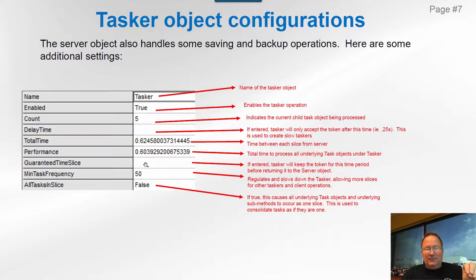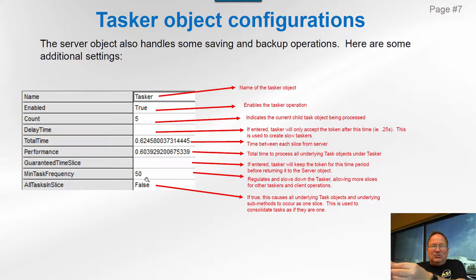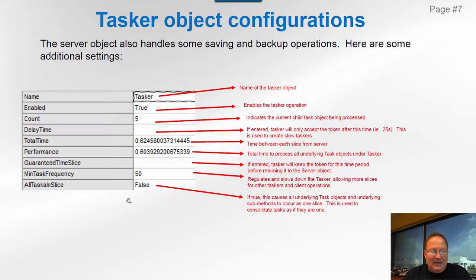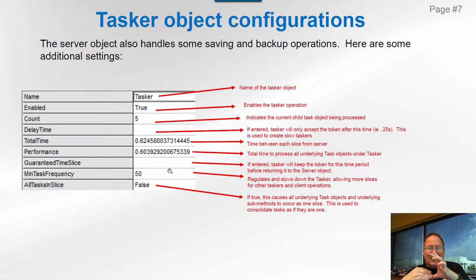Guaranteed time slice is an amount of seconds that dedicates a certain amount of time for that tasker when it gets a token. Minimum task frequency is a way of slowing down a tasker — it tells it 'don't do any more than 50 underlying tasks in one second.' Note that's underlying tasks, not task objects. You can also tell the tasker not to pass back the token at all until all tasks under the tasker are done in one slice — that's rarely used, but it's used when you want a very quick operation of a bunch of tasks, typically combined with a delay time.